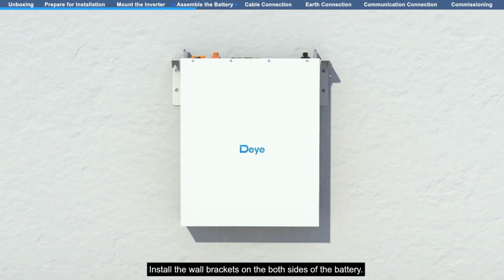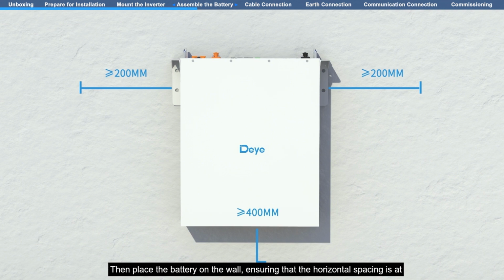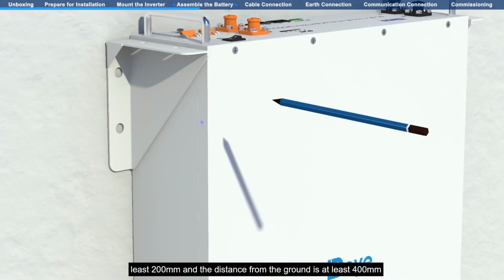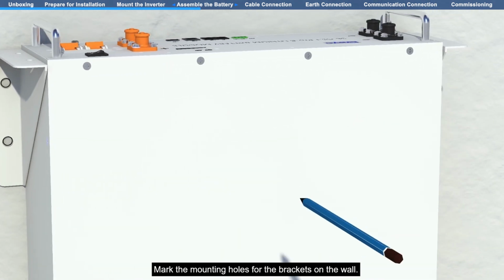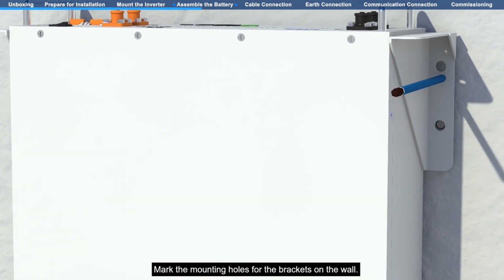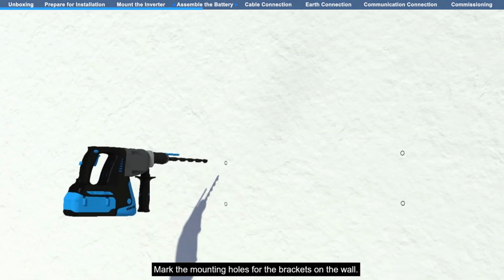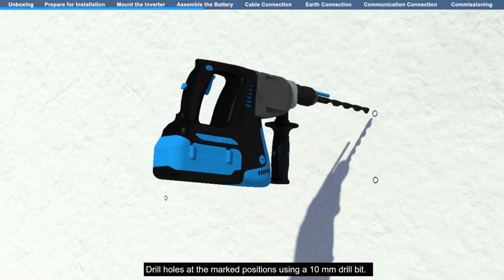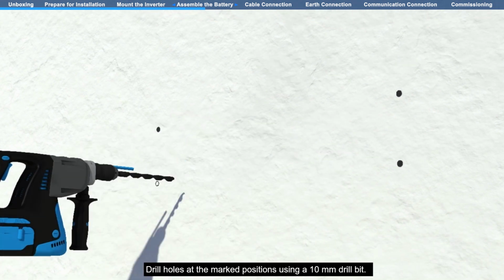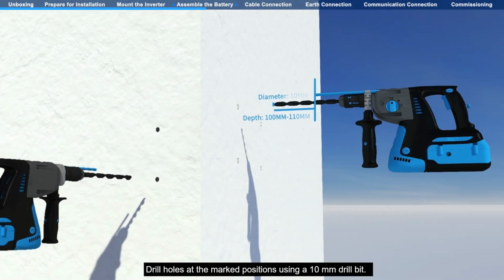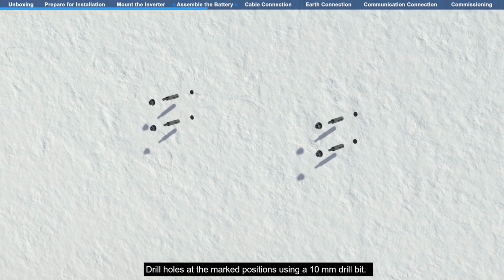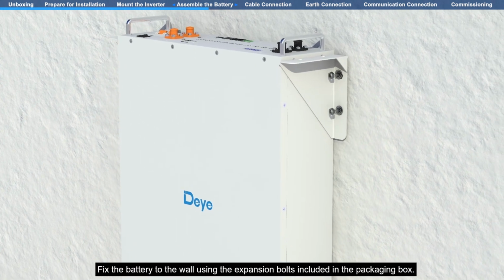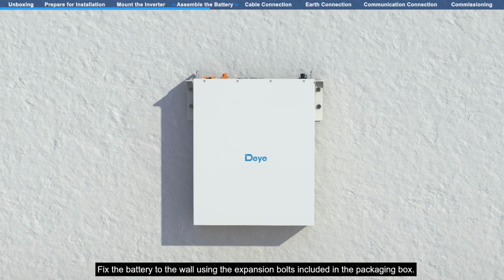Assemble the battery for wall-mounted installation. Install the wall brackets on both sides of the battery. Then place the battery on the wall, ensuring that the horizontal spacing is at least 200 mm and the distance from the ground is at least 400 mm. Mark the mounting holes for the brackets on the wall. Drill holes at the marked positions using a 10 mm drill bit. Fix the battery to the wall using the expansion bolts included in the packaging box.